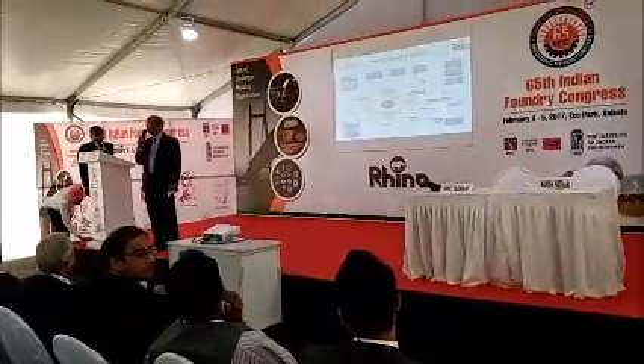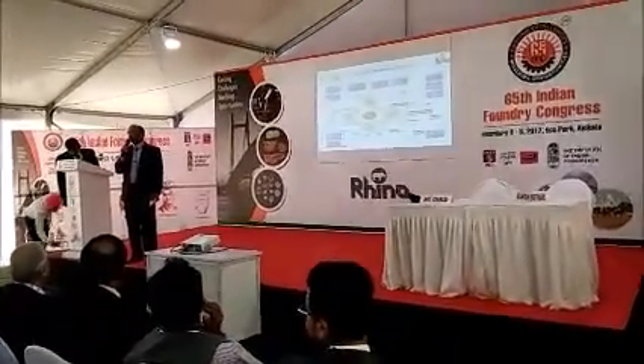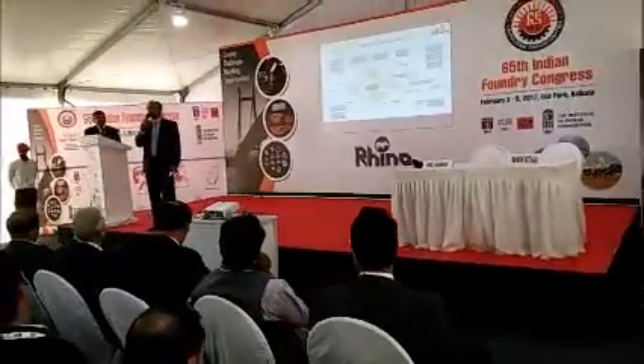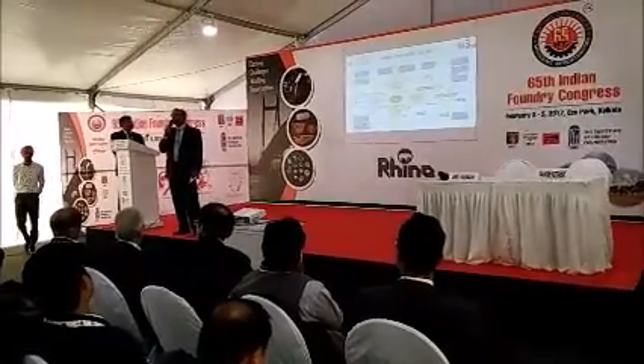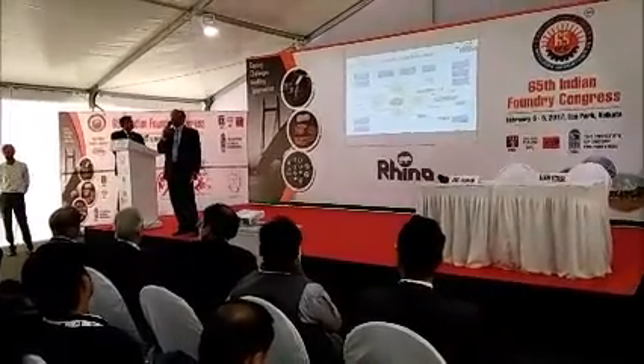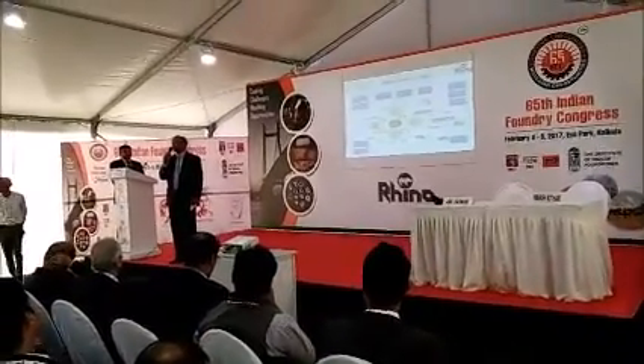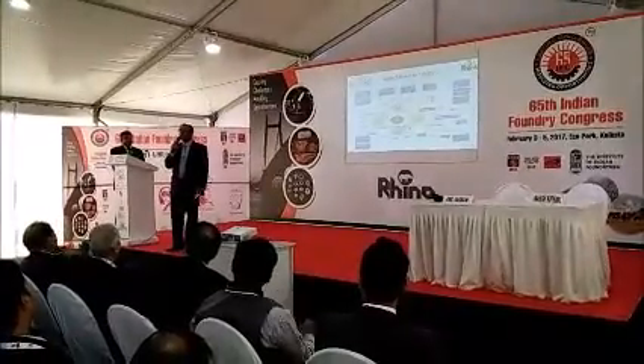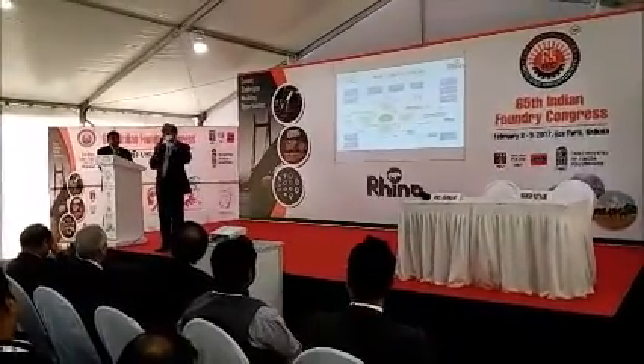Furnace running at full power always gives better productivity, better melt rates. But is it running at full power? Suppose you have a 500 kilowatt furnace running 24 hours. Are we consuming that much energy? At what time was the power drawn less than 500 kilowatt? If you draw less than rated kilowatt, your production is affected. Definitely, you will get a lower melt rate. So all these graphs can be made available as real-time data. Sitting here also, you can see in your foundry at what kilowatt the furnace is running.